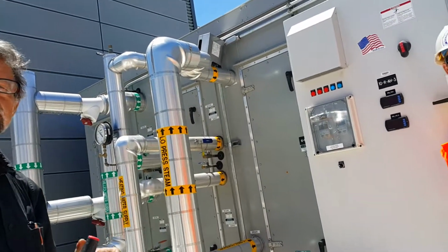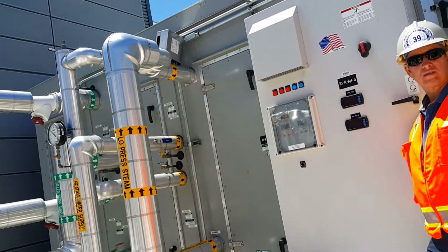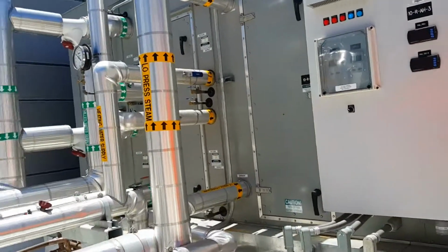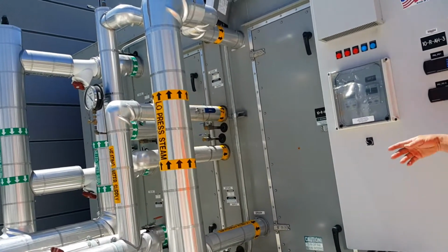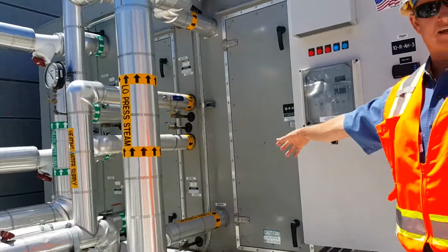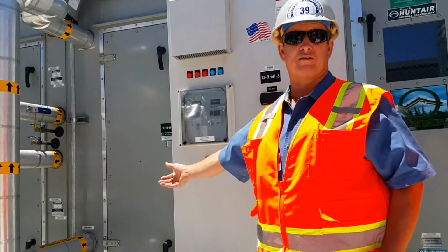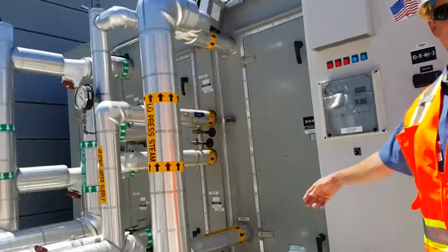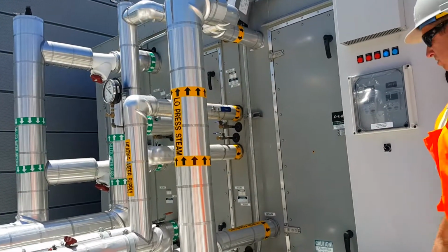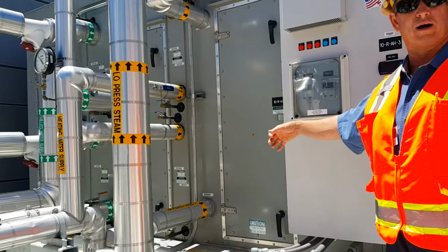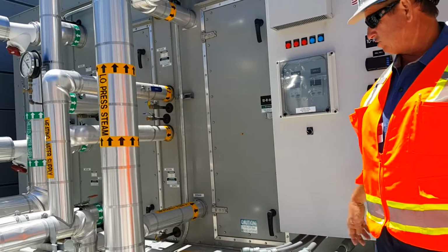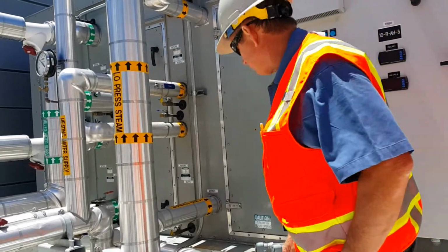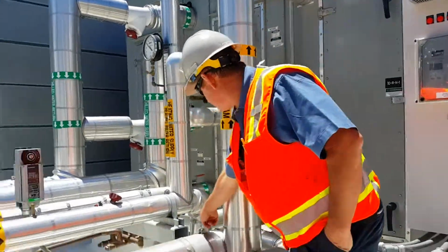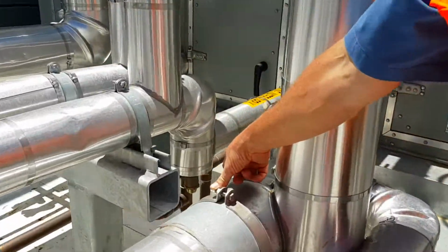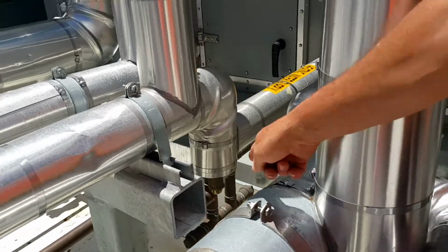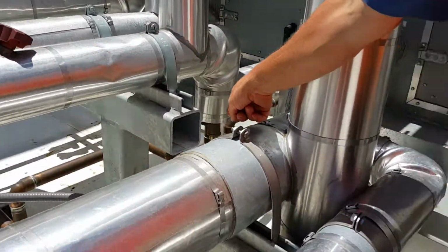Can you show us how to clean the pan, or do you guys know already? Right, you just gotta open the door and you'll see the pan under the coil, and we're gonna get in there with probably some hot soap and water and start at one end and just push it through. Then when you get to the other end, we'll put a bucket in the pan and let it force, try to rinse it out. We've got traps, well this is the steam, we got a trap right there that we can clean, because any of the debris that we push and wash through, we can open up the cleanouts down there, and then it'll drain to the trap.